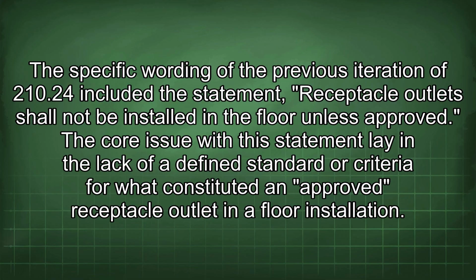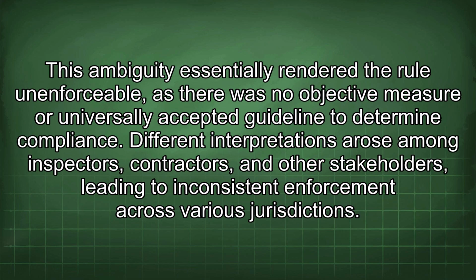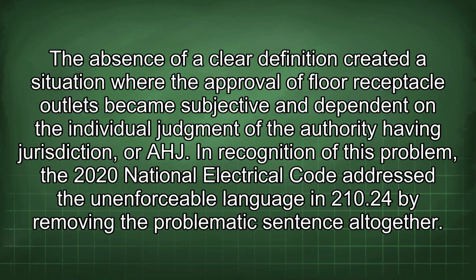The core issue with this statement lay in the lack of a defined standard or criteria for what constituted an approved receptacle outlet in a floor installation. This ambiguity essentially rendered the rule unenforceable, as there was no objective measure or universally accepted guideline to determine compliance. Different interpretations arose among inspectors, contractors, and other stakeholders, leading to inconsistent enforcement across various jurisdictions. The absence of a clear definition created a situation where the approval of floor receptacle outlets became subjective and dependent on the individual judgment of the authority having jurisdiction, or AHJ.